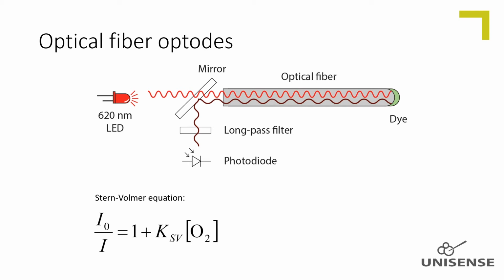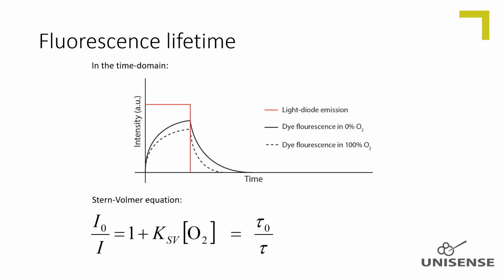The fluorescence intensity is, however, a function of the amount of the excitable dye, and when illuminating the dye, a bleaching process starts, and thus the intensity measured for a given oxygen partial pressure decreases over time as a function of the bleaching. Therefore, it is utilized that the lifetime of the back-emitted fluorescence after an illumination pulse is also oxygen dependent, the so-called fluorescence lifetime.